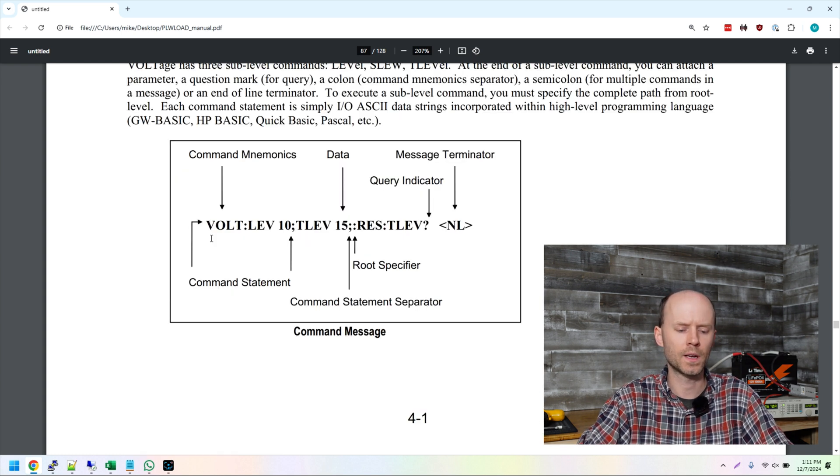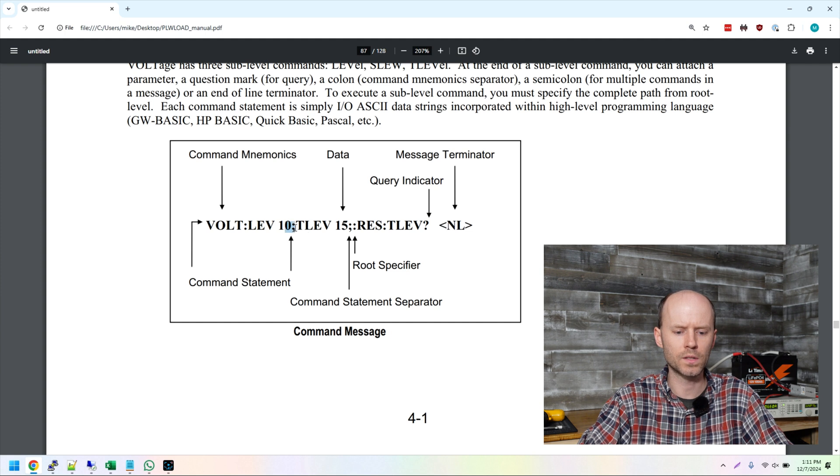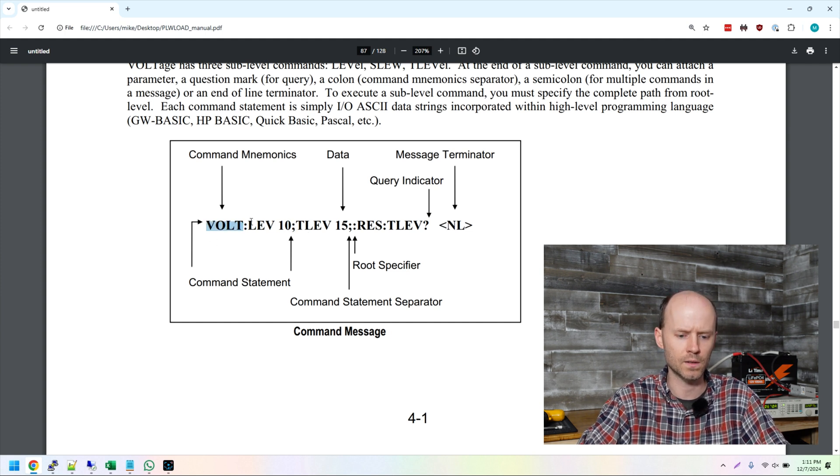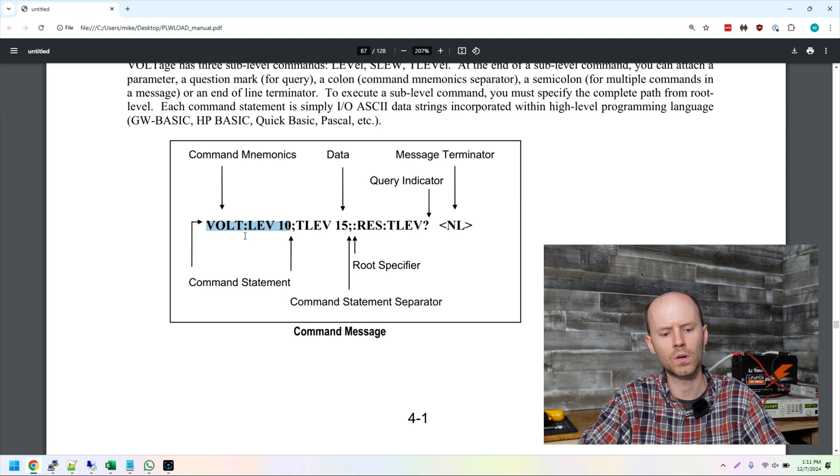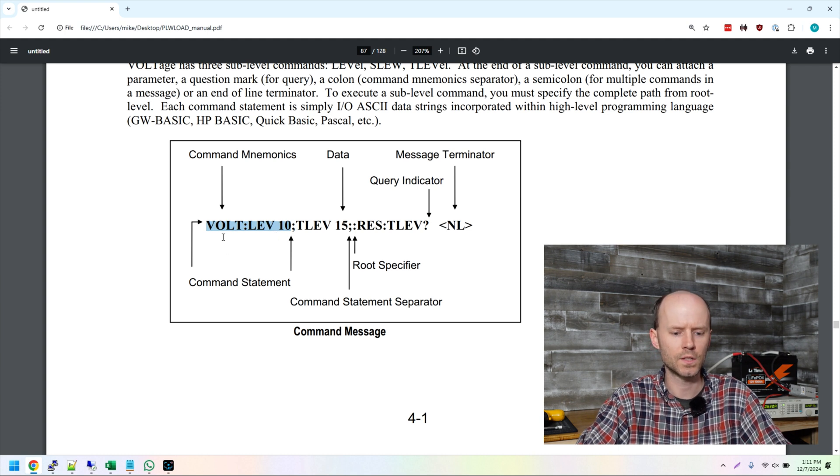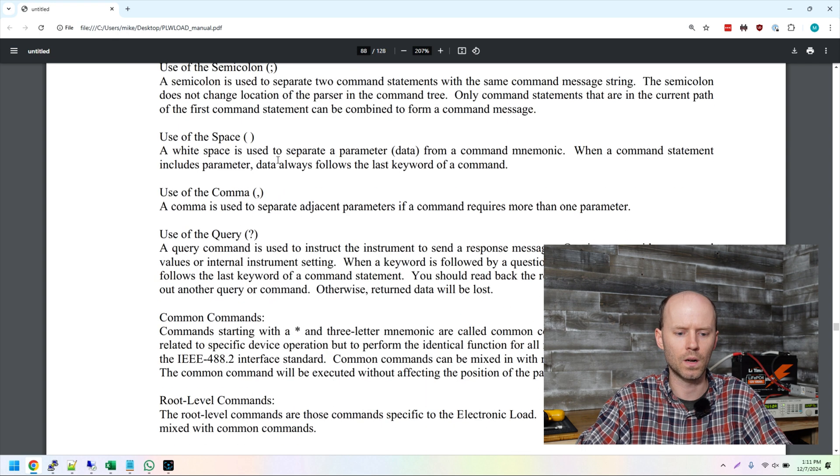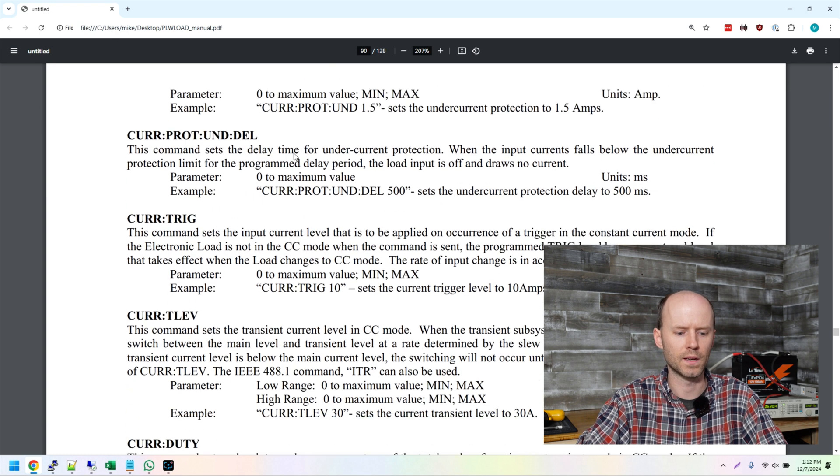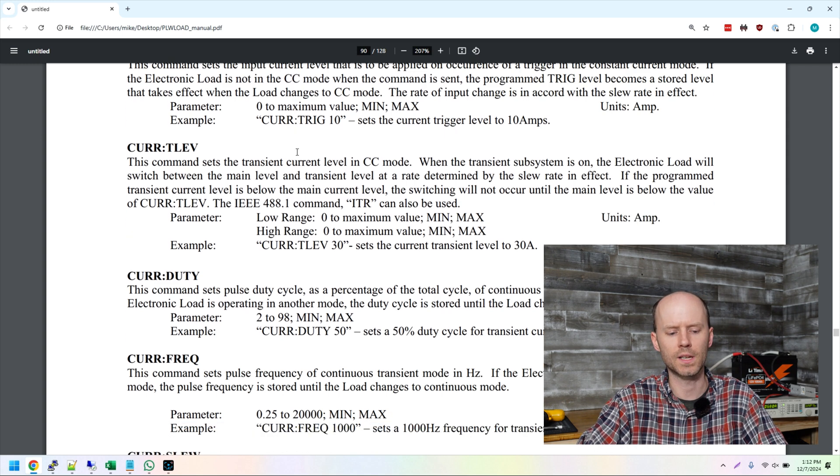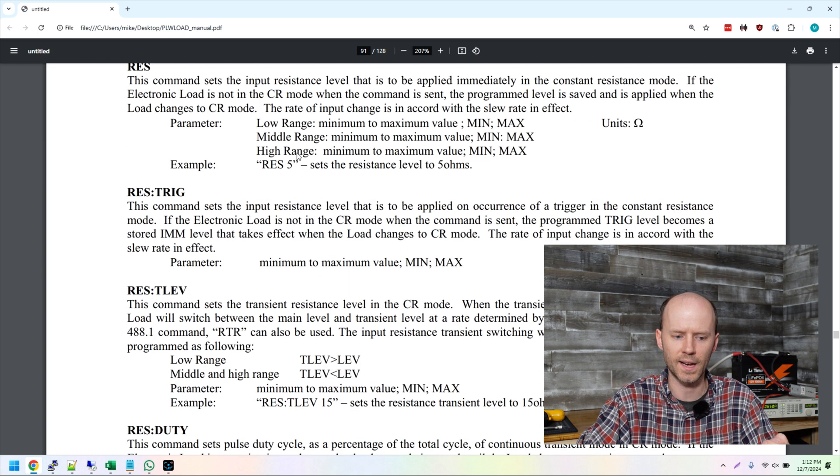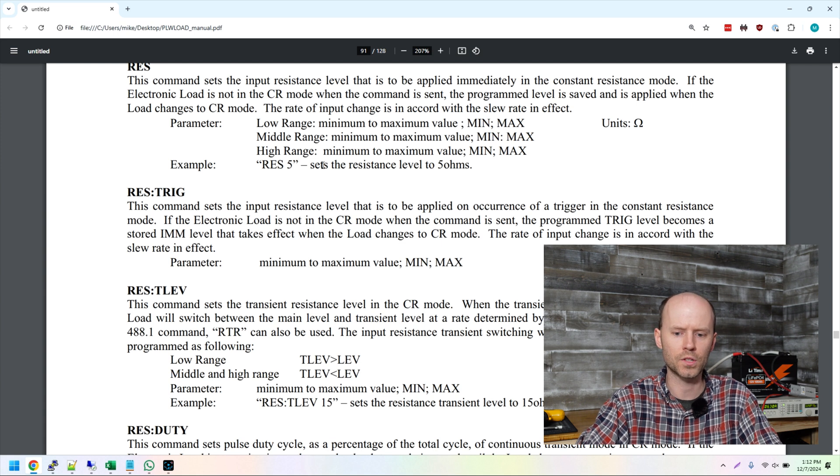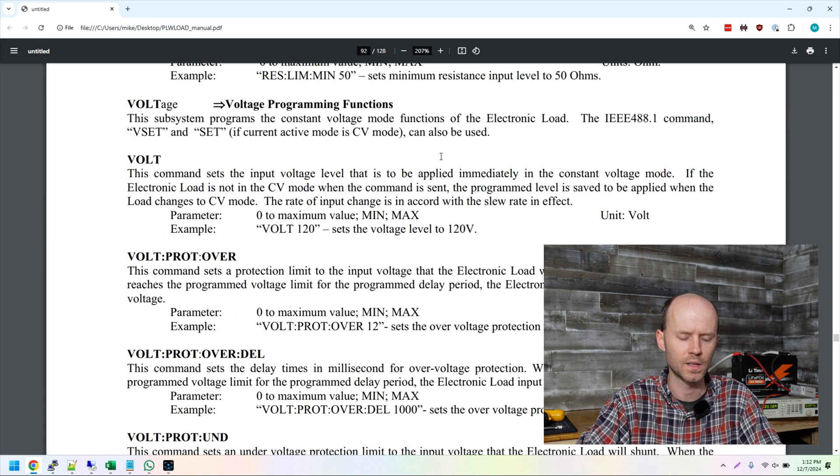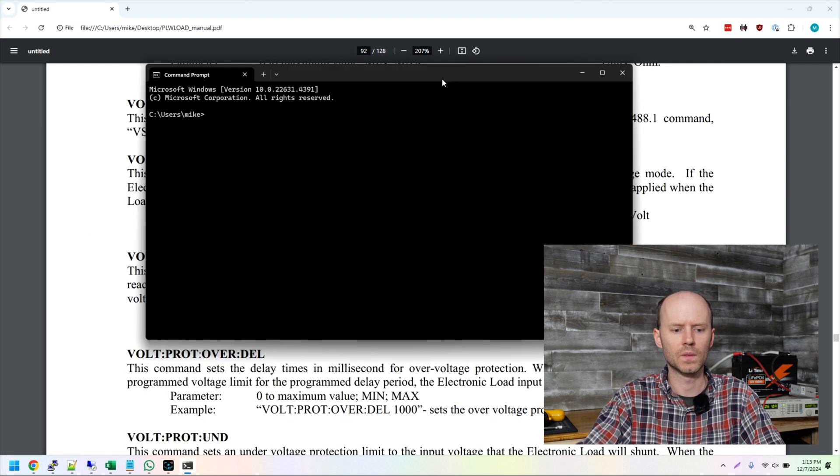So here we can see a fairly complex example of a command. The semicolon denotes there's multiple statements together. All we want to do is run a single command. And for that, an example is going to be volt colon lev 10, voltage, a sub command. And then if there's any parameters with that, this example is a 10. So all of the syntactical information is explained here. And I'm not going to go through this diagram. I'm just going to give you some example commands. But like I said, everything is laid out here exactly. The command, the shortened version, how you use it, what it does, what it returns, the units. So we're just going to jump straight over to a telnet prompt.